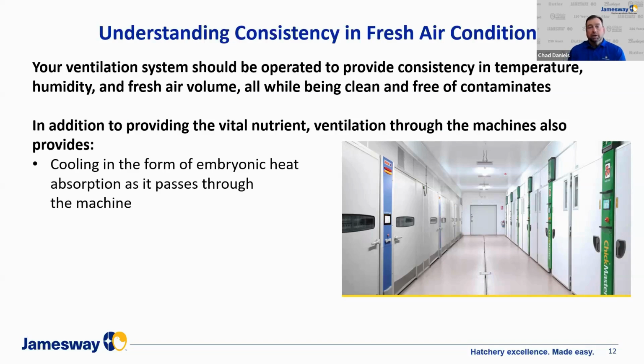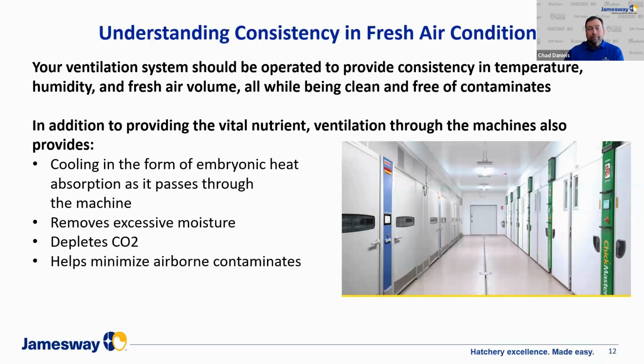So from an incubation manufacturer's perspective, we build a machine that we know is going to require ventilation because it needs that vital nutrient of oxygen. And if we're going to have to provide that vital nutrient to the machine, what else can we do with that air? In this case, we consider it a form of cooling to the machine. It also removes that excess moisture that we talked about, the air exchange through the machine. That also helps deplete CO2 and then helps minimize airborne contaminants.